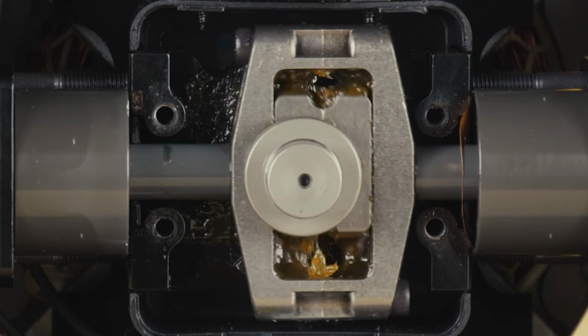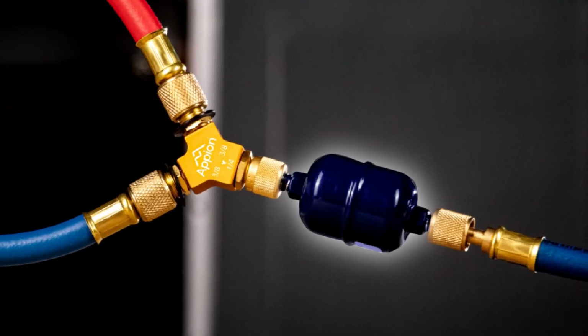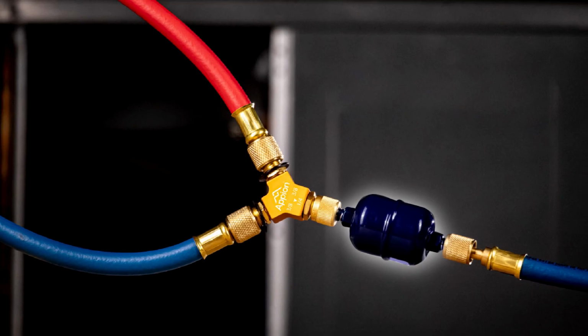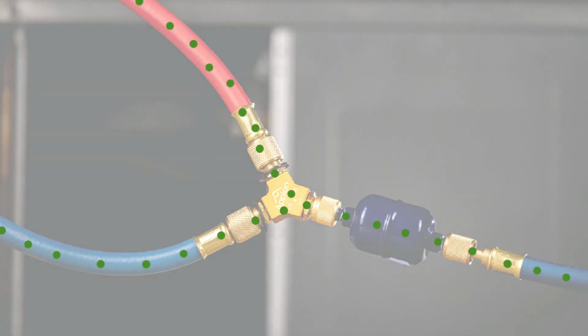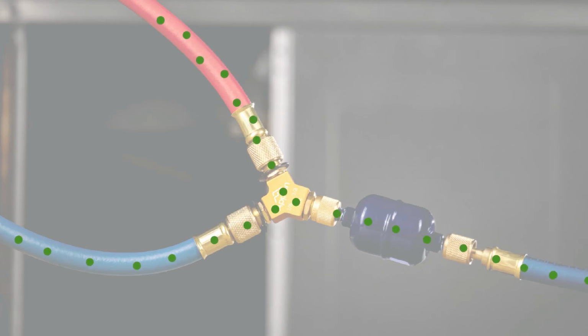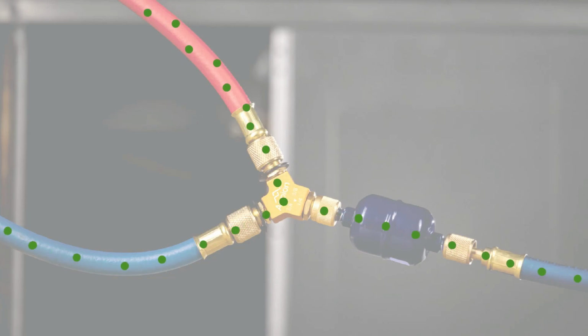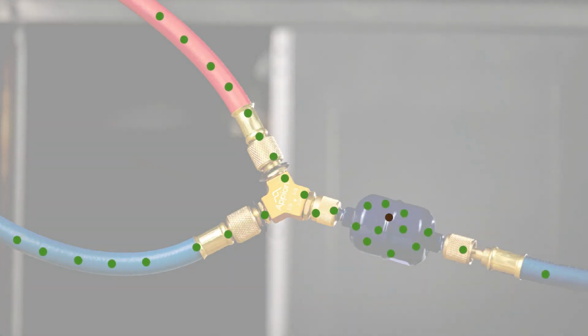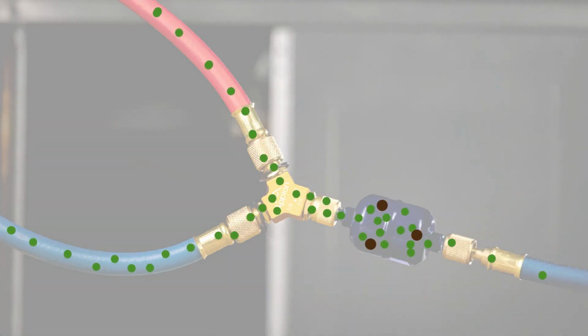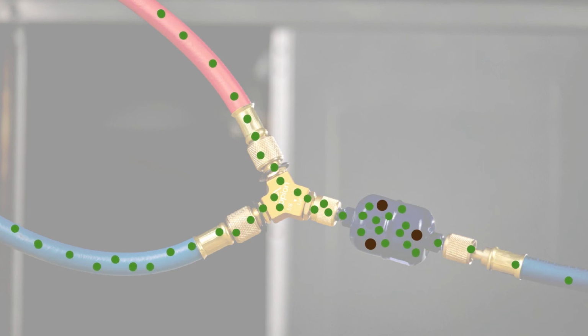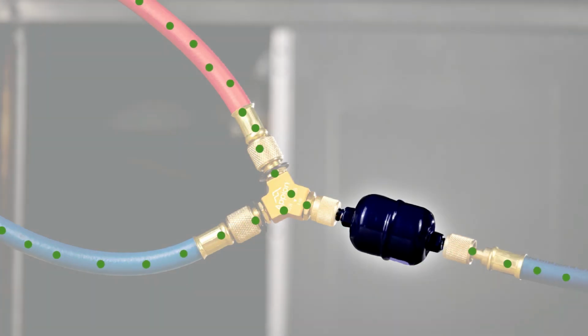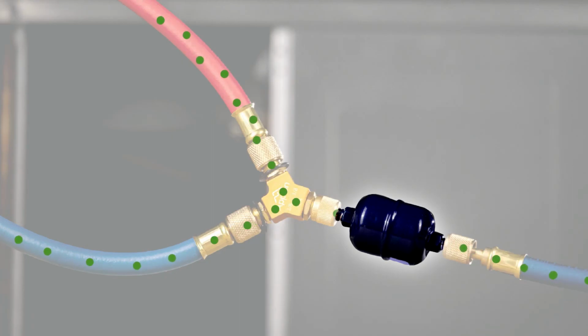Another important element of your refrigerant recovery setup is the filter dryer. Its primary role is to safeguard the recovery machine against debris and contaminants rather than cleaning the refrigerant itself. This is especially important while servicing systems that are wet, have undergone a compressor burnout, or are otherwise contaminated. Failing to replace the filter dryer can lead to painfully slow recovery times and refrigerant cross-contamination. Therefore, as a best practice, it is highly recommended always to use a filter dryer and regularly replace the filter dryer between jobs to ensure the longevity and efficient operation of your recovery machine.